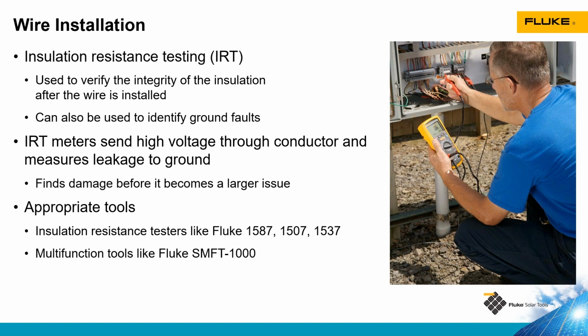Fluke has a wide range of tools that can perform this test, from the handheld multimeter size insulation resistance testers like the 1587 and the 1507, one of which is pictured here on this slide. They will test up to 1,000 volts, so they can do 1,000 volt insulation resistance tests. The 1537 is a new product. It will test up to 2,500 volts in 100 volt increments from 250 volts to 2,500 volts.